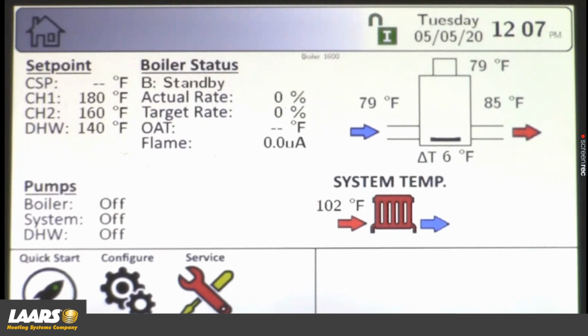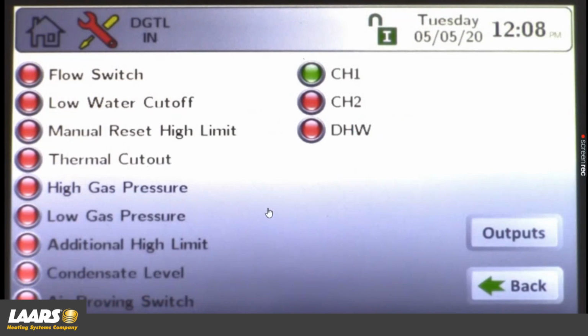All right, so I apologize. I was trying to stop the video there. I wanted to show you something. On this screen, what I'm using here is a simulator for this example. So this is not a simulator for a Pennant. An example of that, we do not have a thermal cutout on a Pennant boiler. We do not have a condensate switch on a Pennant boiler. But the point being, everything is in sequential order here. Flow switch first, low water cutoff, manual, high limit, etc. So I'll continue to play the video.